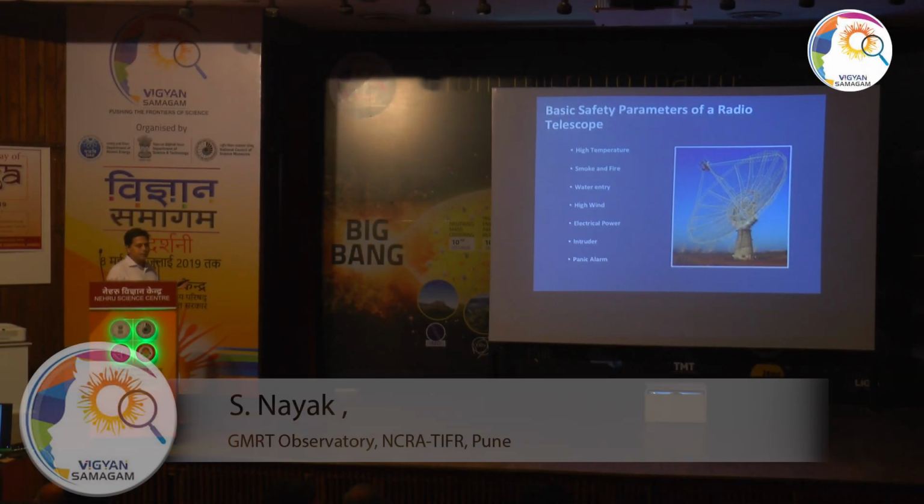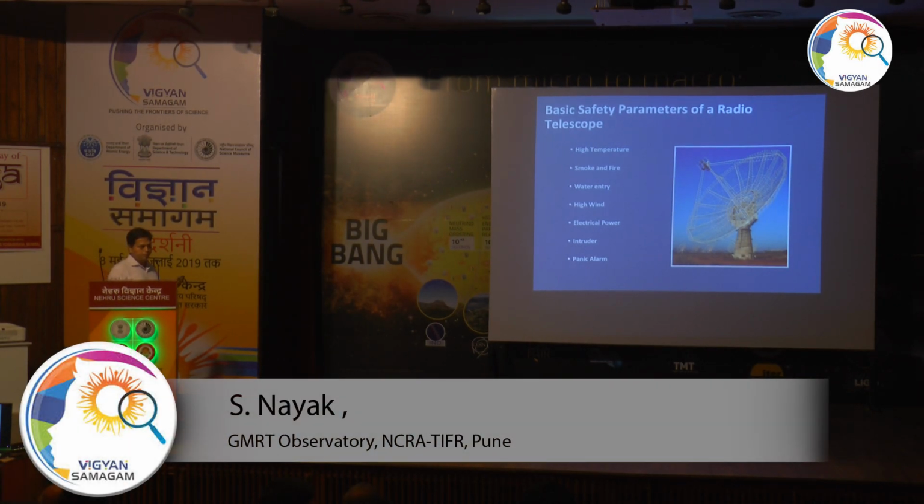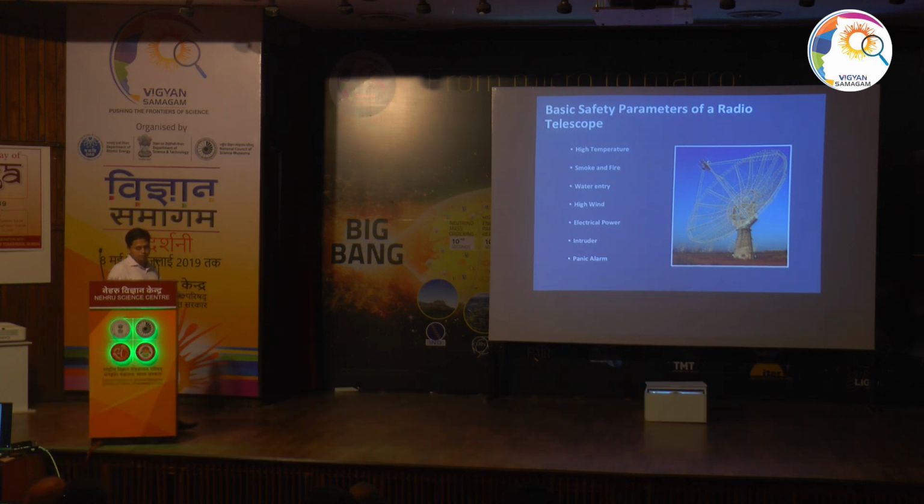Control the shell temperature, the antenna base shell temperature, between 22 degrees and 28 degrees. We have AC plants over there. If it goes beyond 28 degrees, the antenna will stop working. It alarms first. When it starts alarming after 28 degrees, it will wait until it reaches 30-31 degrees, and after that, the antenna will stop its working and shut down all the systems there.